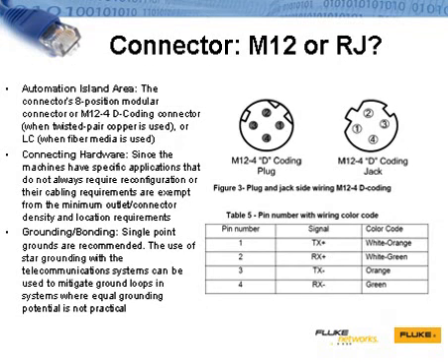Also, the TIA has an addendum for the industrial premises. This is the TIA 1005, and this introduces the M12 connector and permits up to 6 connectors of either RJ45 or M12 within each channel. The addition of 2 more connectors will inevitably reduce the performance of the overall link. When this topology is used, the channel test becomes critical. And with more connections, the grade of the components like cabling, connectors, and patch cables used are even more important.